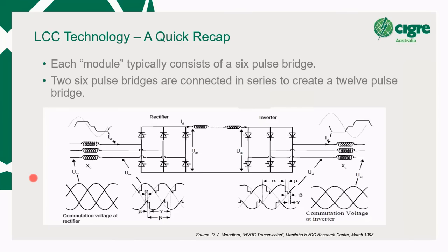Okay, and basically the AC network causes each of the thyristor valves to commutate at various times, leading to this kind of waveform here. It's got a DC waveform. Reversing this process allows an AC waveform to be created, although you will expect a fair amount of harmonics in the voltage that's created, and this requires a significant amount of harmonic filtering.